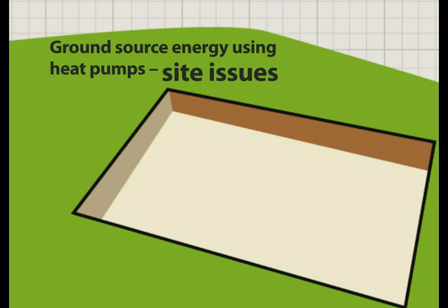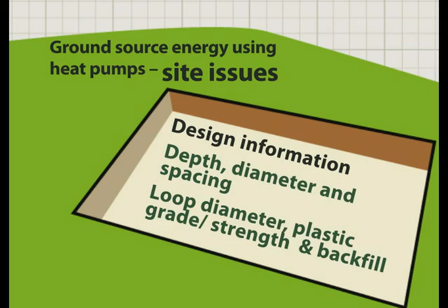First, there needs to be adequate investigation of site geology and ground conditions. Is there a ground investigation report and groundwater information? Has a test borehole been sunk? Has proper design information been provided? For a closed loop system, has depth, diameter and spacing been specified? For the installation, what is the loop diameter required, plastic grade and strength, and backfill specification? And what sort of quality assurance will be put in place for the scheme?